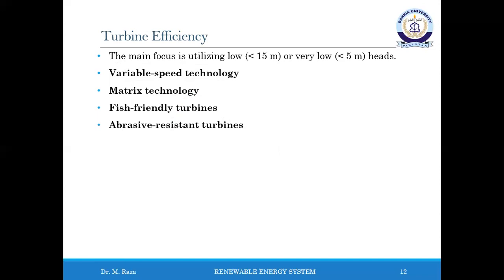Another new technology is matrix. This technology aims to develop small identical compact turbine generator units to be inserted in a matrix-shaped frame. The number of units in the matrix can be adapted to available flow. During operation, it will be possible to start and stop any number of units. Thus, the units in operation will always run under optimum flow condition. This technology is well suited to installation at existing structures such as irrigation dams, ship locks, etc., where water is released at low head.